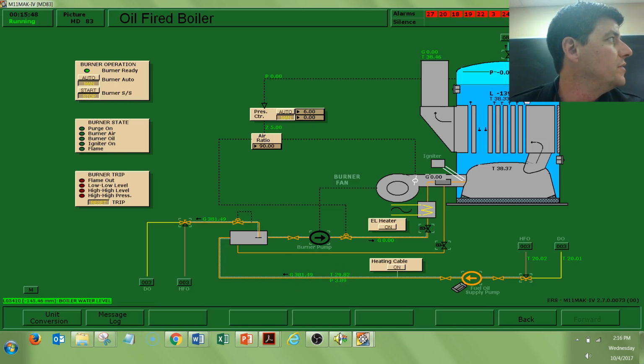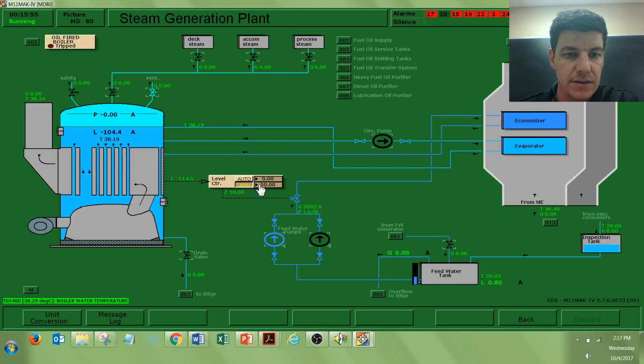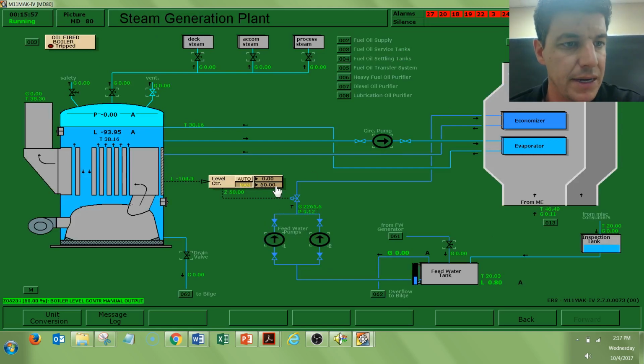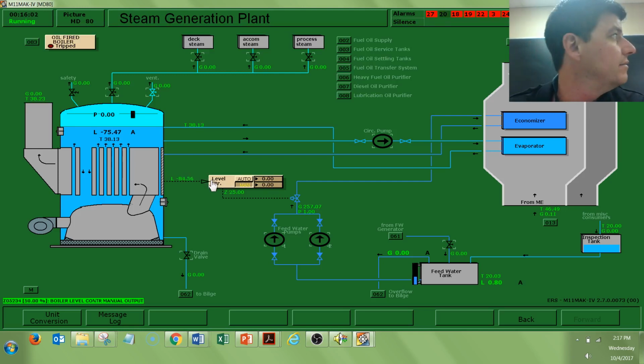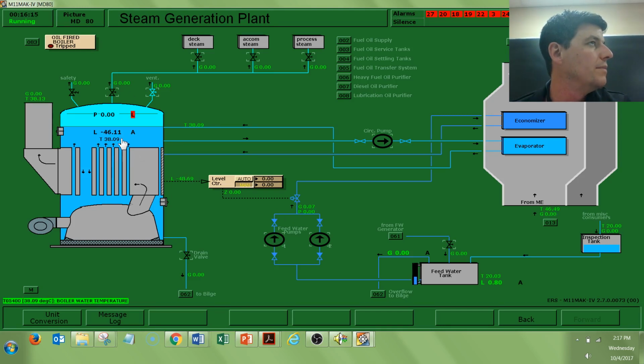Check on my boiler level. Looks like I'm getting closer to my target, so backtrack. And we'll turn off my feed water pump. And I can close off my flow control valve. Usually don't want to leave my feed water pump running against a closed valve if I know it's going to be a 20-minute process or hour-long process to warm up, so I'll come back and deal with that later on.